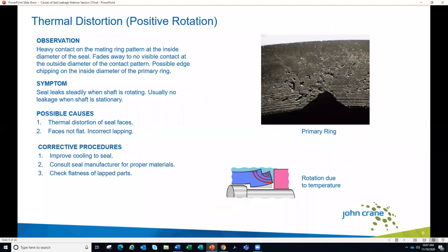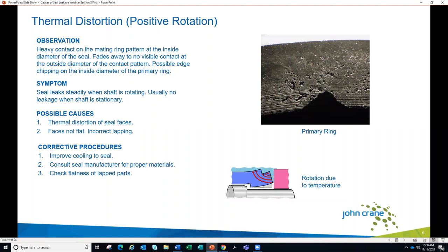Looking at the inverse scenario, we're now talking about heavier contact at the ID, caused by thermal distortion, also called positive rotation. Instead of the faces being closer at the OD, we're seeing them come together at the ID. On the primary ring you would see heavy wear, potential for chipping and cracking at the ID, and then as we move towards the OD, seeing less wear — potentially none depending on the amount of distortion. This can come from high temperature gradients: as materials get hot they want to grow, growing more at the location of heat generation toward the ID, causing those IDs to come together and creating heavier wear and damage at that part of the seal face.